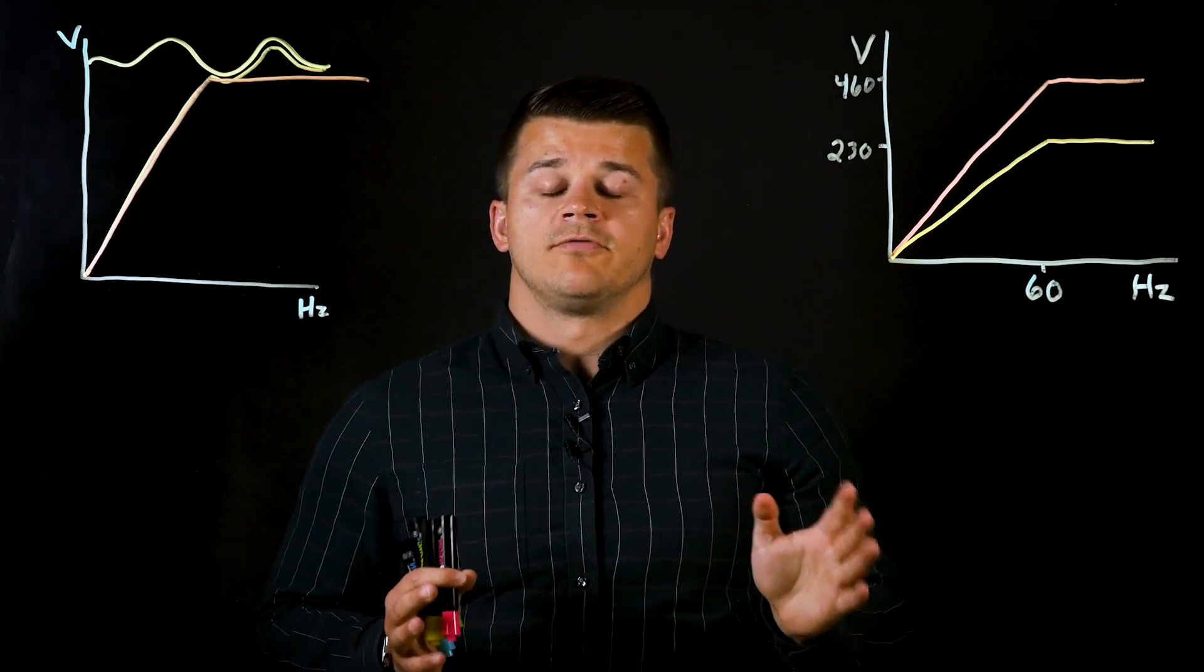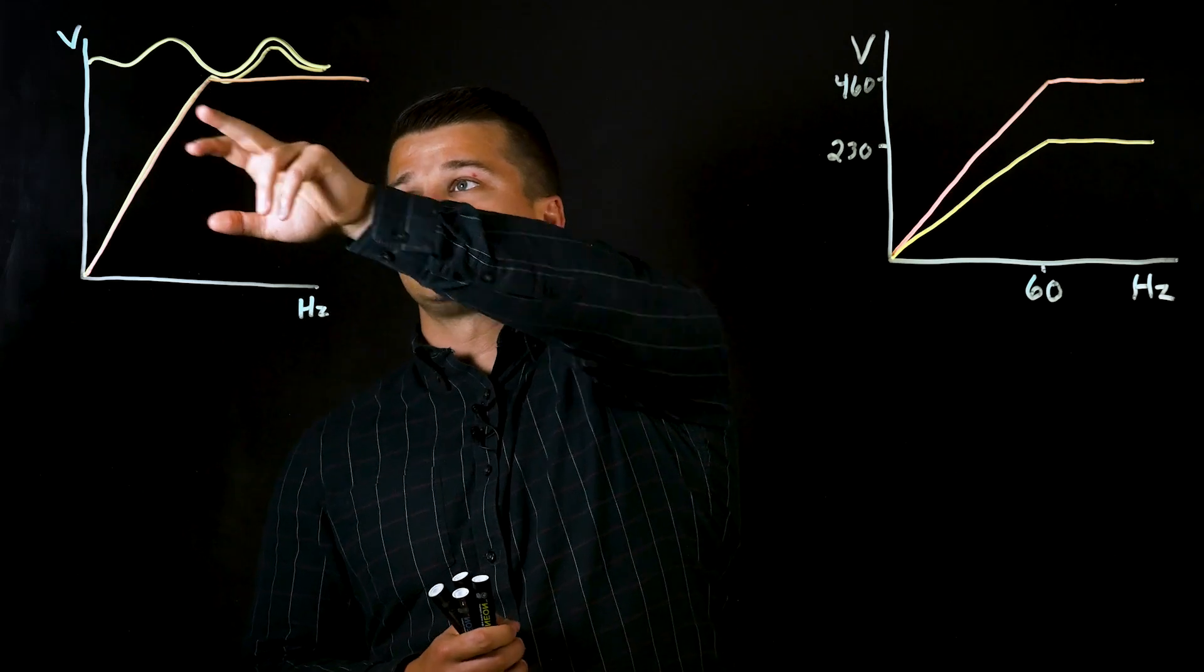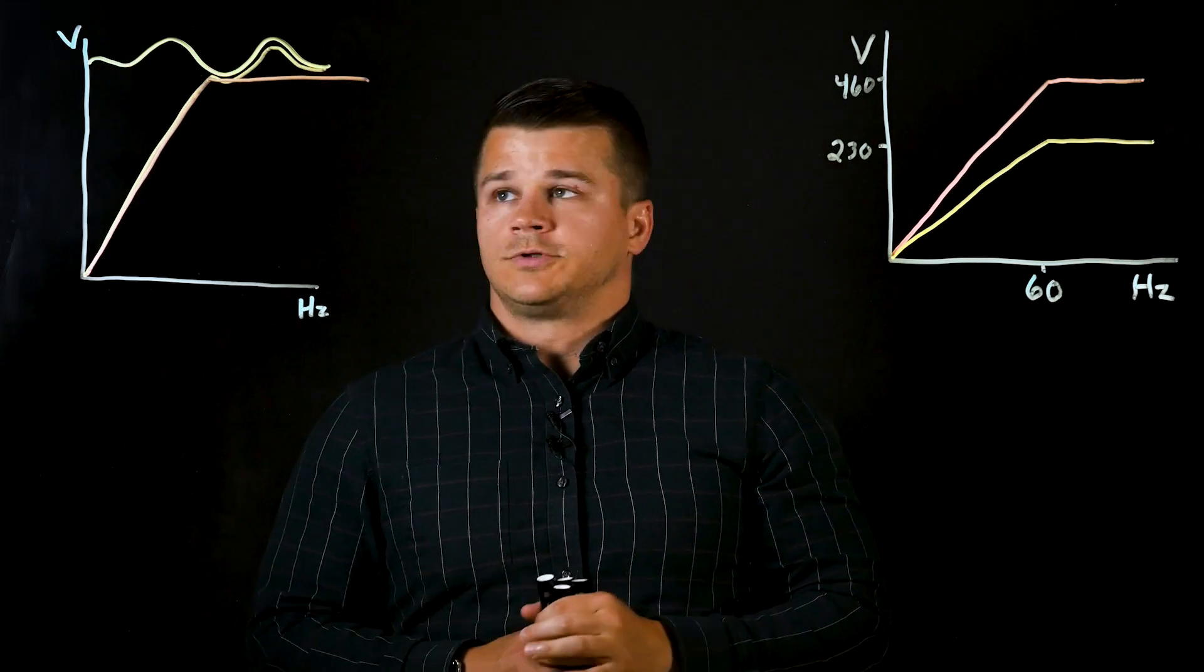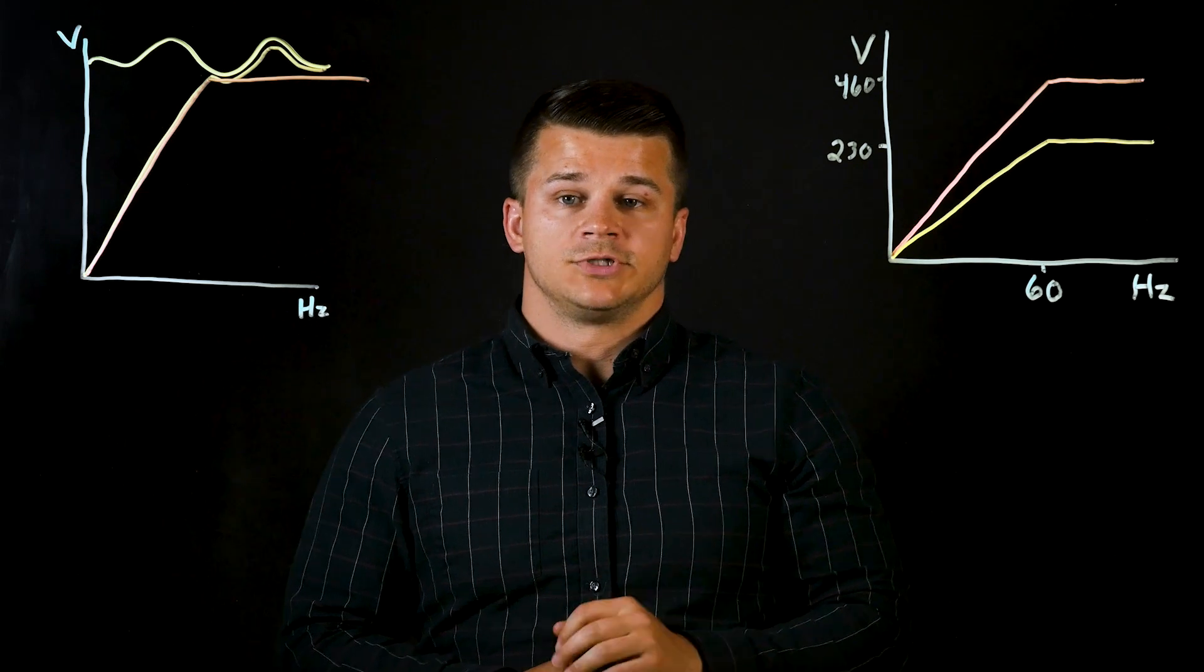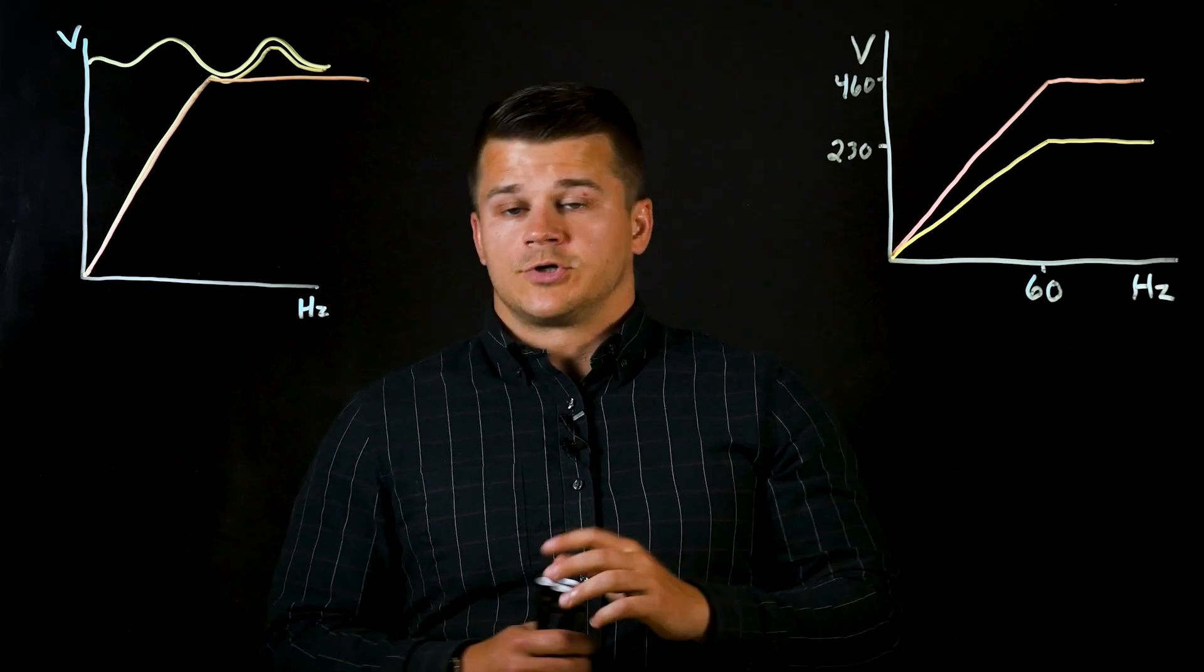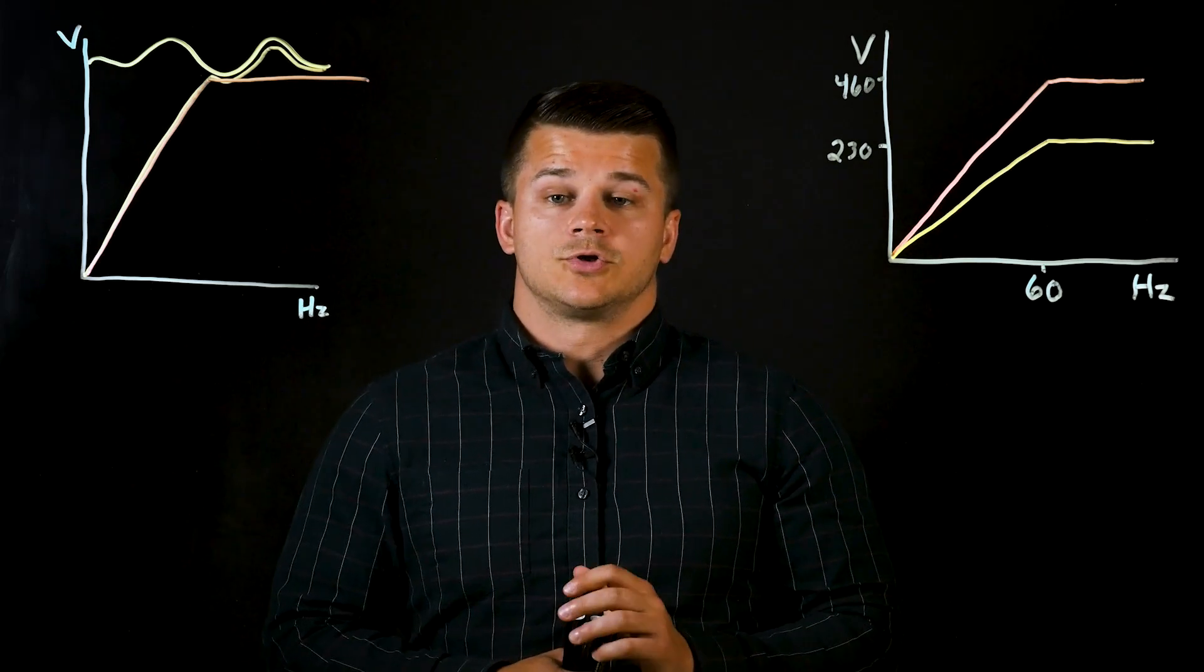Now with the voltage stabilization function activated within the KEB drive, it takes effect once you reach the rated frequency. So if you're running at 60 Hertz and you imagine this is your input rated voltage, without the voltage stabilization your output voltage would simply reflect what your input voltage is to the drive. So it could range anywhere from 420 volts if you have a lagging mains, or if you have a voltage spike up to 528 volts.